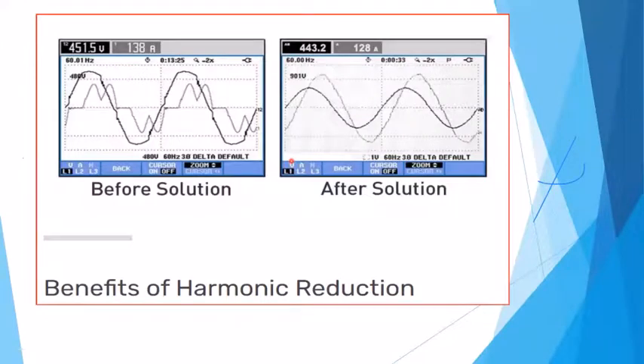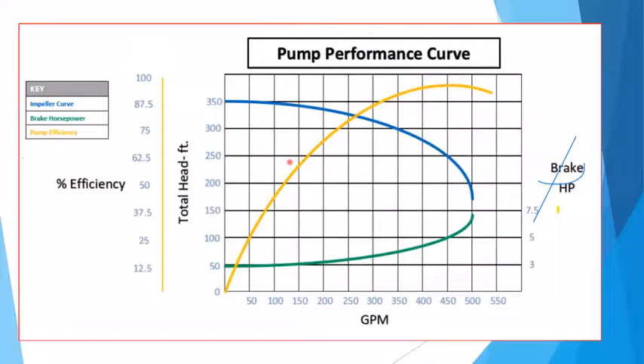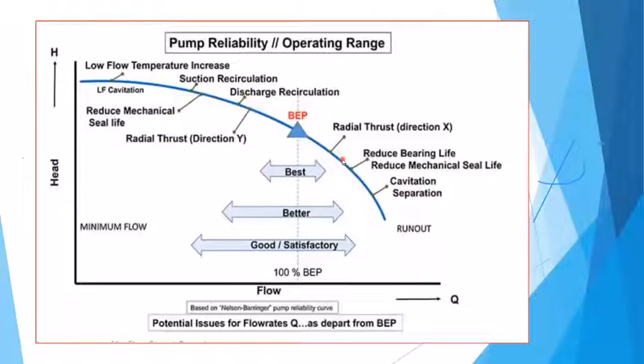So when you're looking at a pump, and this happens to be a pump curve, it's got the brake horsepower. Every motor or every pump has an optimal efficiency point, meaning at a certain speed, certain power, that's where it's the best efficiency. If you're too far back on the curve, the efficiency drops. And it's all based off of the impeller size and the rotating speed of that, and the lift or the amount of pressure that you're bringing back. So you have a certain amount of head pressure that is being fed back. And again, this is the best efficiency point. So that's the optimal point of all of the factors that are operating.